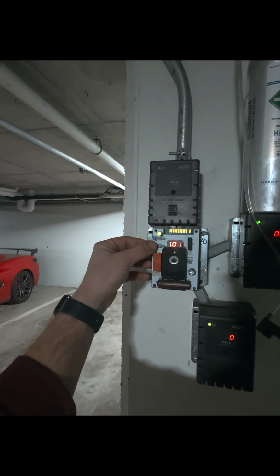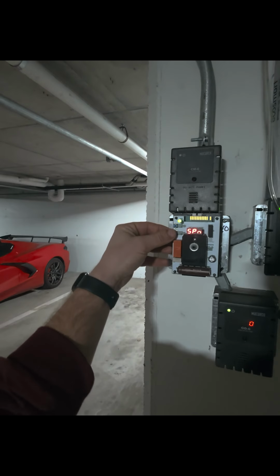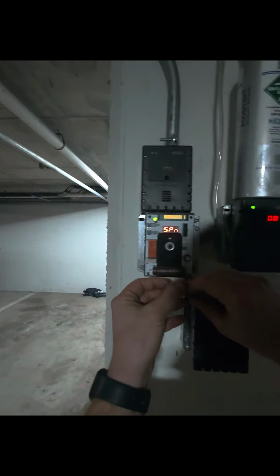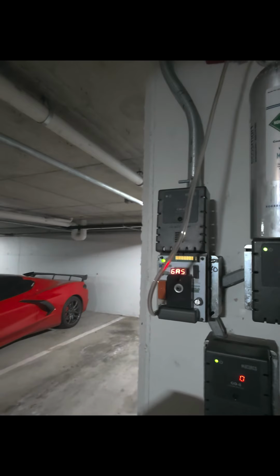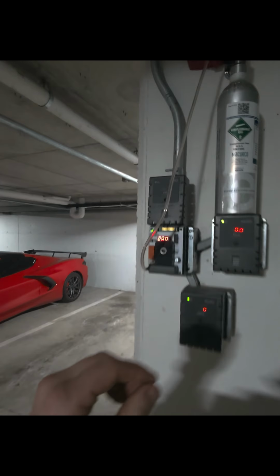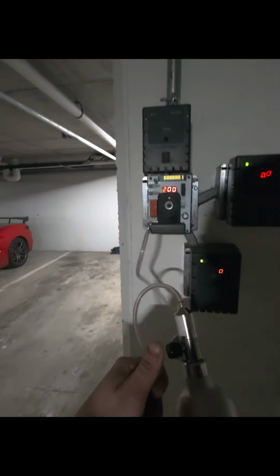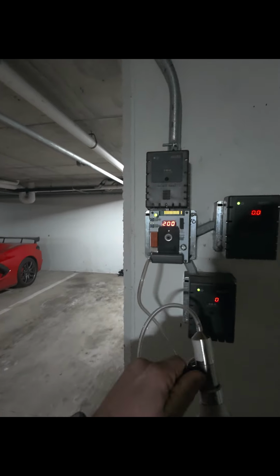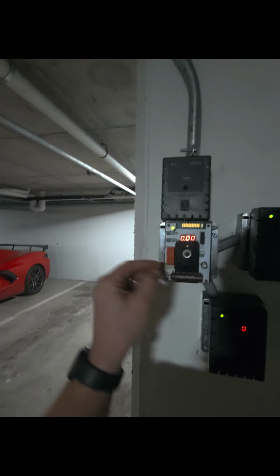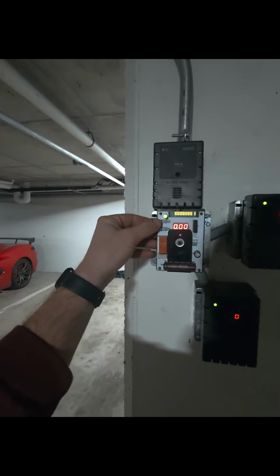So from here you can hit enter, SPN, get this hood over it. Now it's going to run through its calibration process, and then I'll show you that number after the fact as well. All right, we got the pass. So we're going to go ahead and shut this gas off. ESC, you can see that that code has been reset, obviously because we just calibrated it.